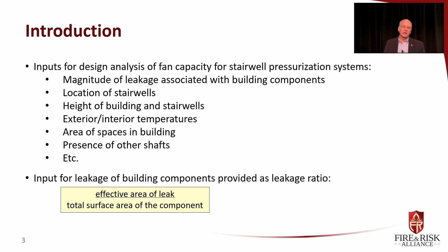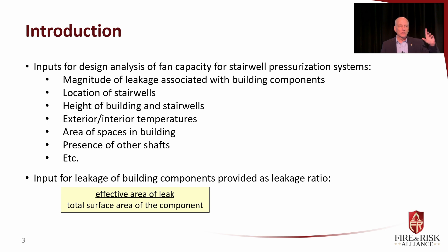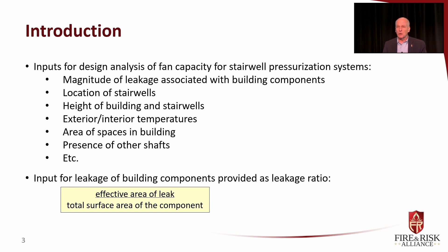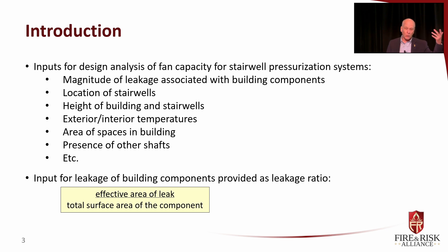The inputs for design analysis of fan capacity for stair pressurization include, whether one is doing hand calculations, using the CONTAM model, or using the Ventus model — the most contemporary of the list. It includes the magnitude of leakage associated with building components. Every building component leaks and that leakage needs to be accounted for, whether it's an exterior wall, an interior wall, a stairwell wall, a floor, or a roof.